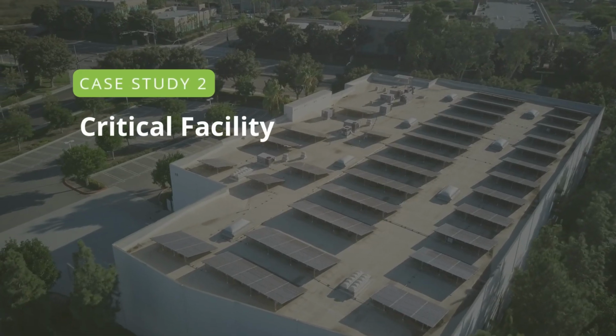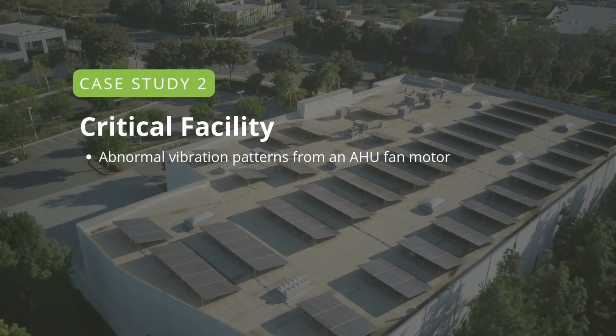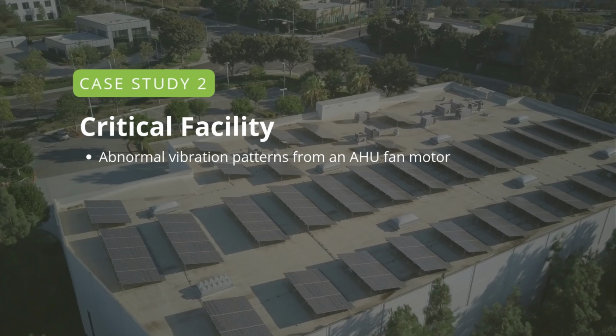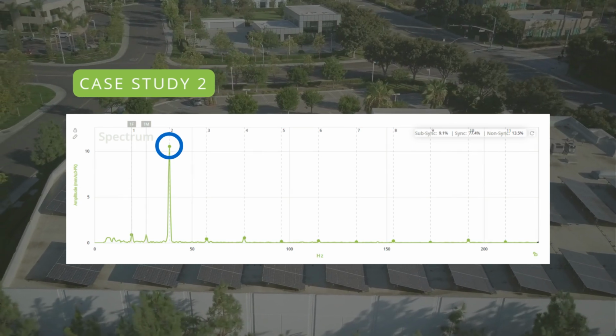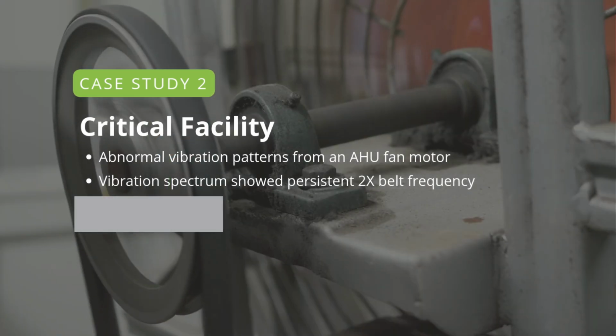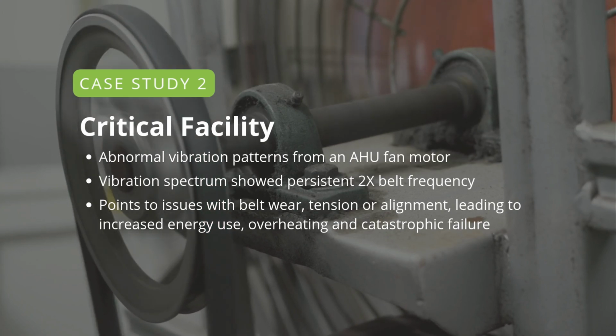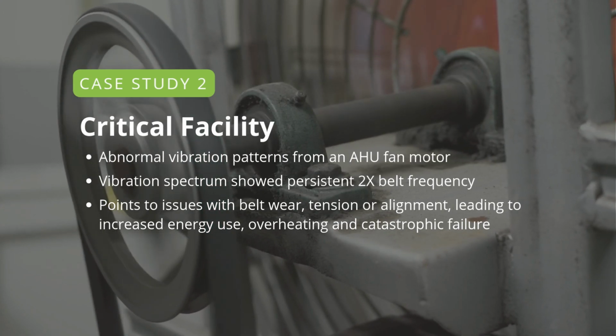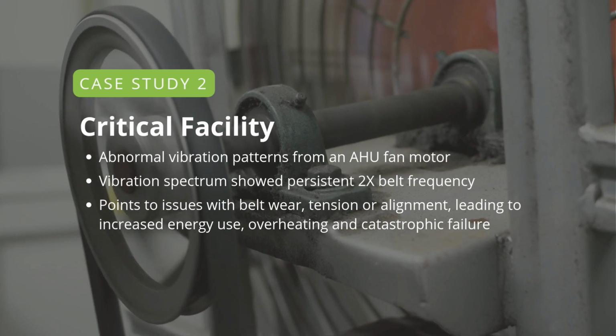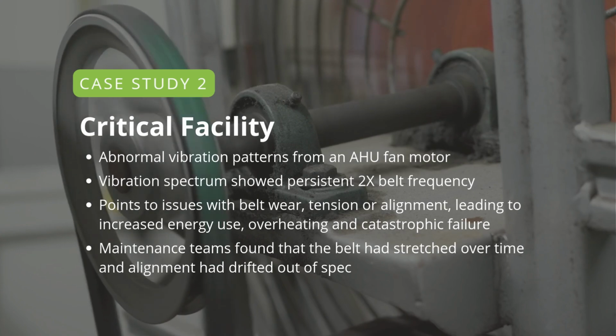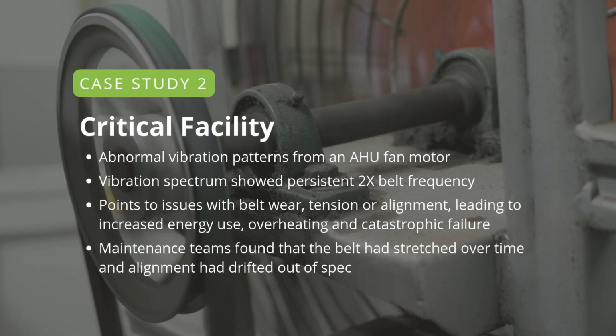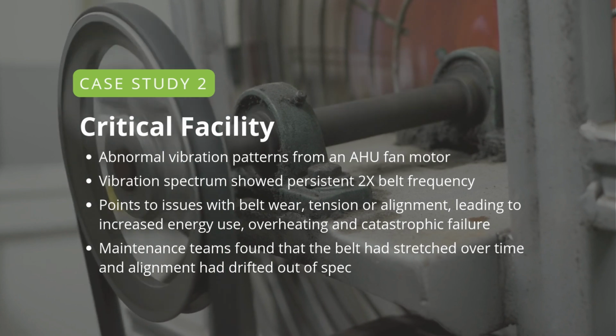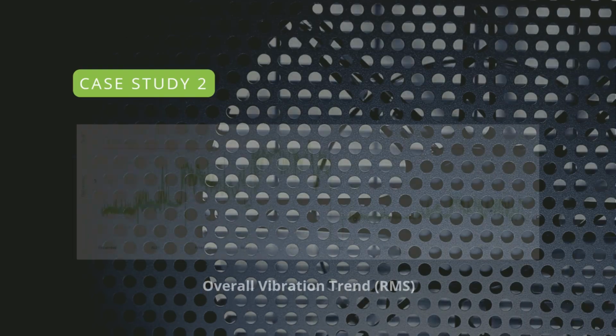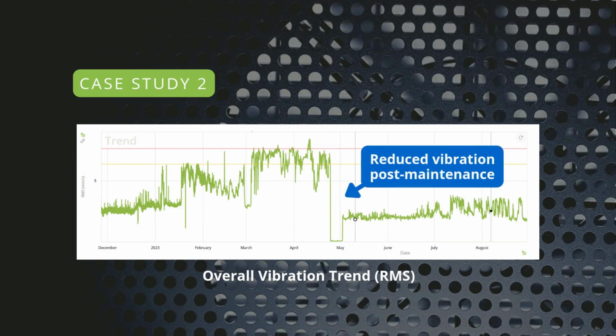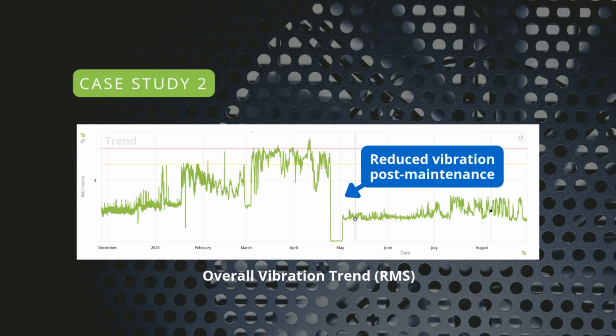At another facility, engineers began noticing abnormal vibration patterns coming from an AHU fan motor. The overall vibration level wasn't excessive, but the vibration spectrum showed a persistent 2x belt frequency. This kind of signature often points to issues with belt wear, tension, or alignment, all things that can lead to increased energy use, overheating, and eventually a catastrophic failure. Maintenance teams took a closer look and discovered that the belts had stretched over time, and the alignment between the motor and fan pulleys had drifted slightly out of spec. By correcting both issues, the facility was able to restore normal operation and eliminate the risk of a potential failure down the road.